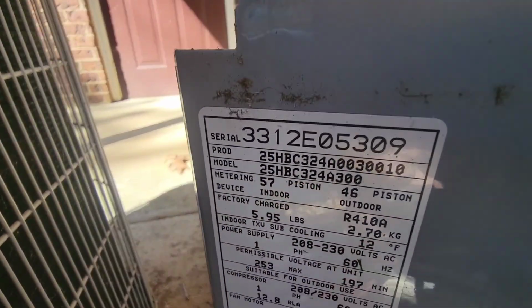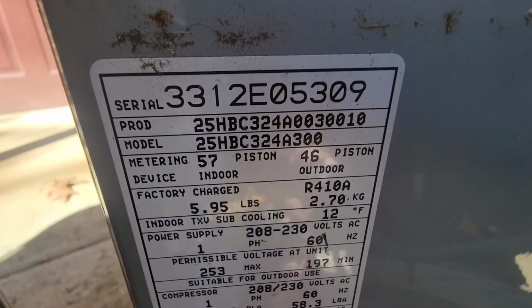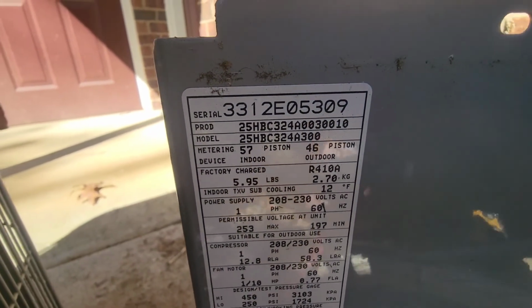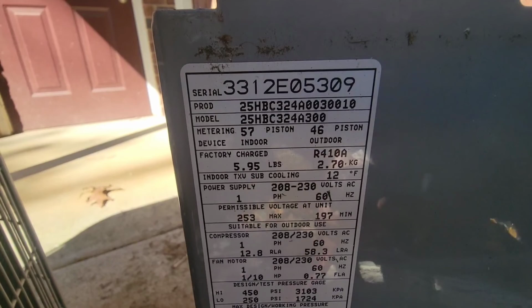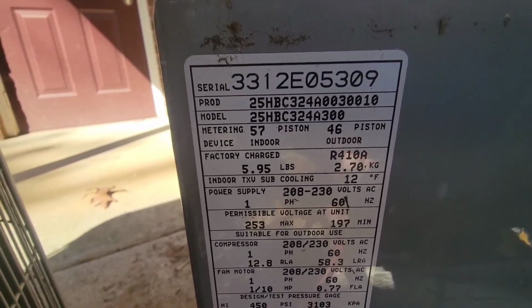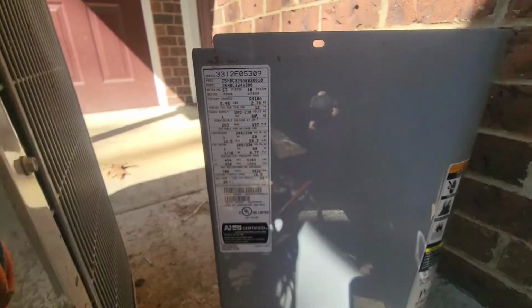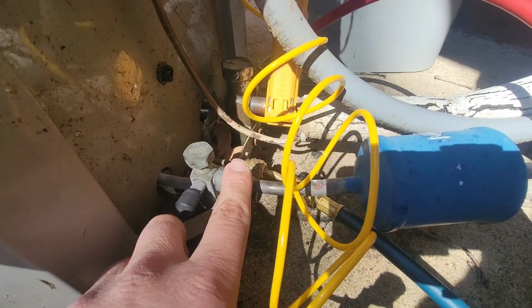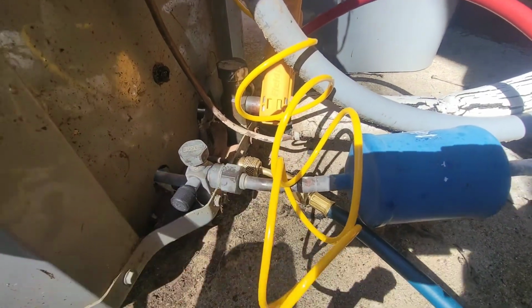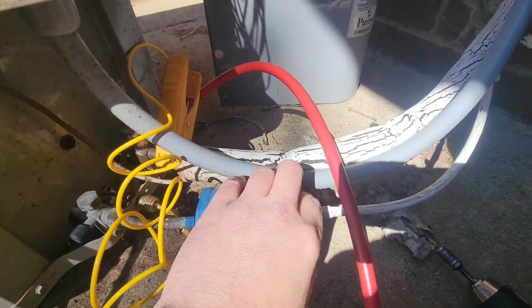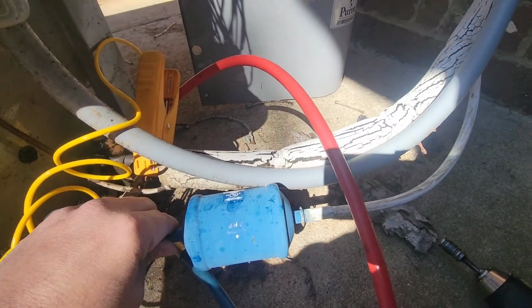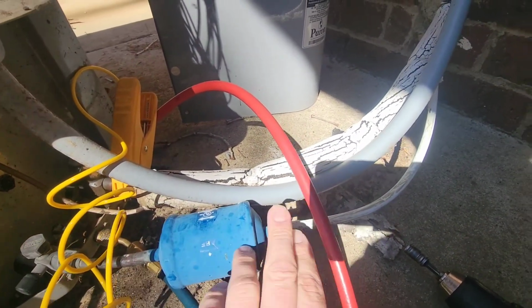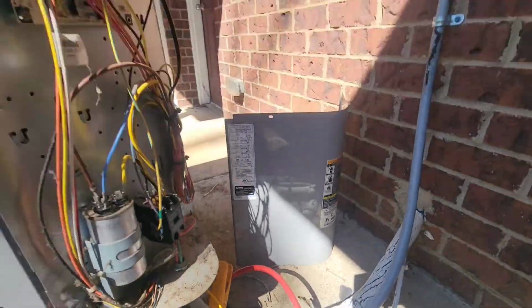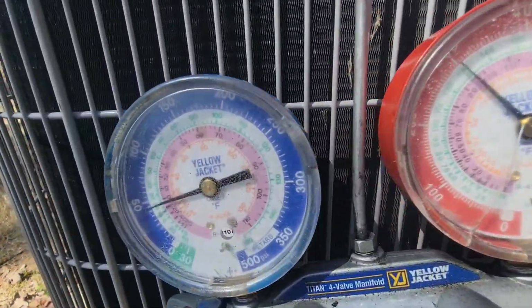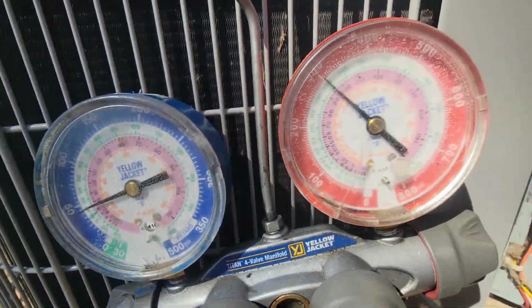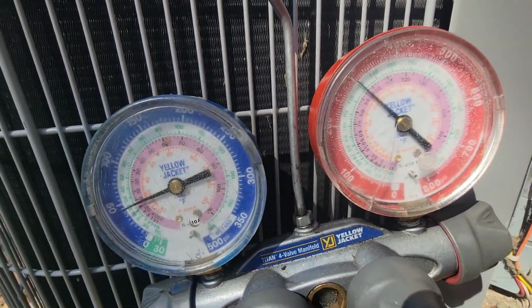This is a 24,000 BTU unit. So 25 HBC 324. So it's a 2-ton unit. It's got a piston. And where's that piston metering device? Right here. Okay. It's got a filter dryer. You need to check across it, make sure there's no temperature difference from one side to the other. That way we don't have a restriction. It looks like it was just low with refrigerant so far.